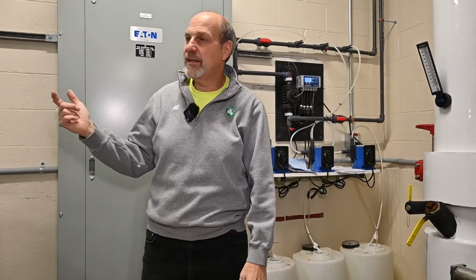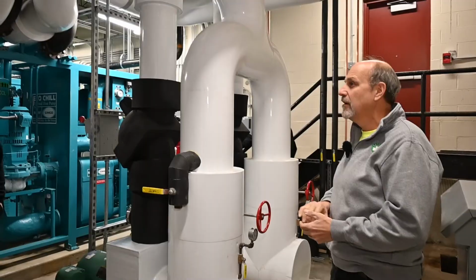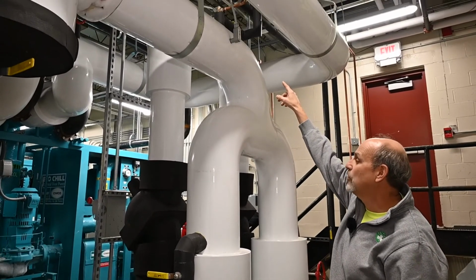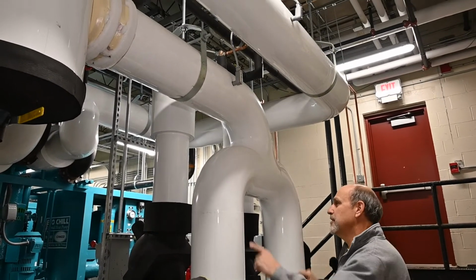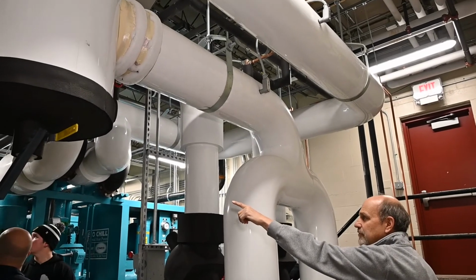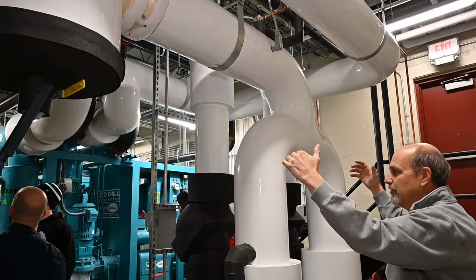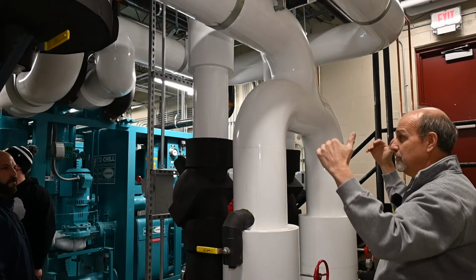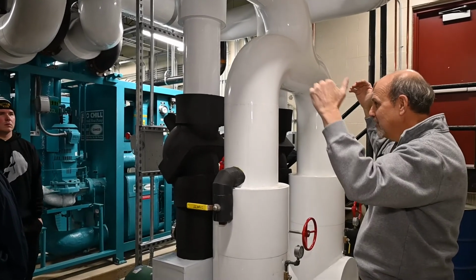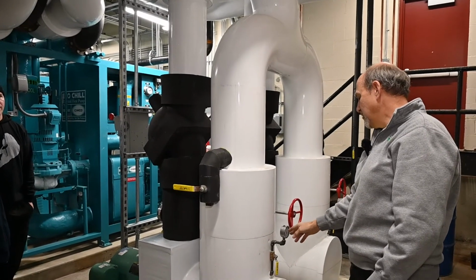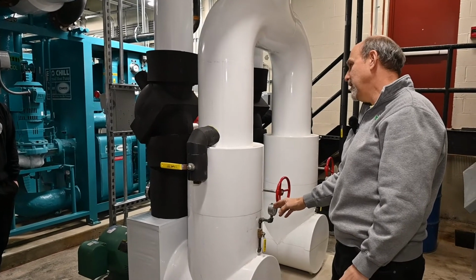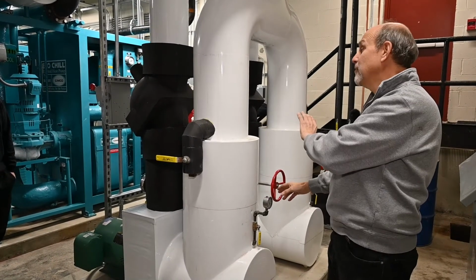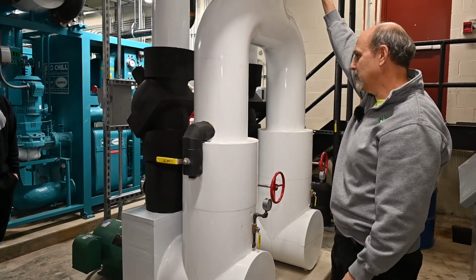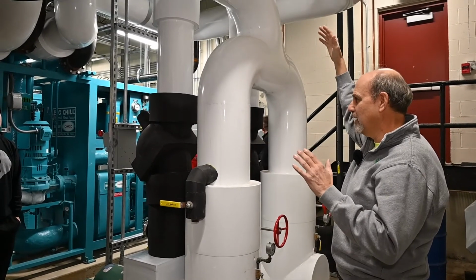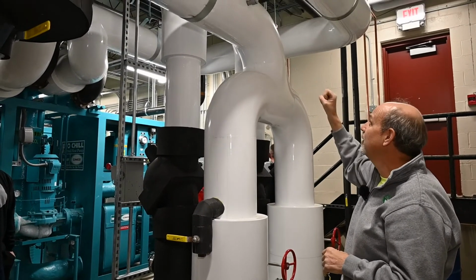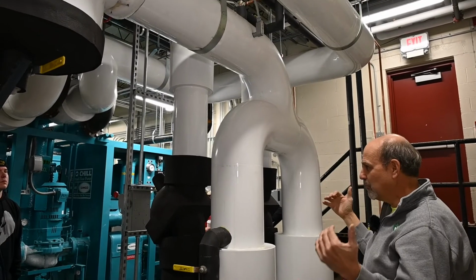The other thing that we had here, and it's a code requirement, on the top of this pipe of the cold glycol loop, and there's another one on the 6-inch warm loop, there's 2 relief valves. In the event that the pressure in this system somehow should go a little higher than it should, we're running at about 1 to 2 psi pressure on the suction side of the pumps. That's set at 25 psi. You should never ever get up that high, but it's a safety measure. If it does, it relieves and dumps that pressure out.